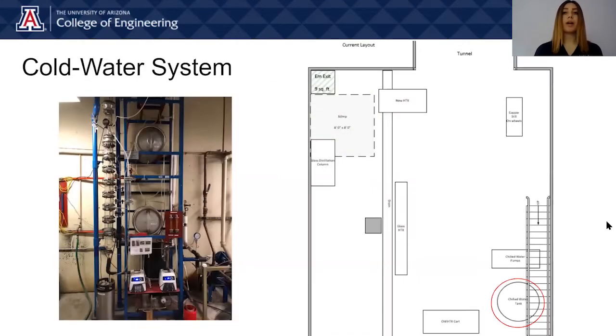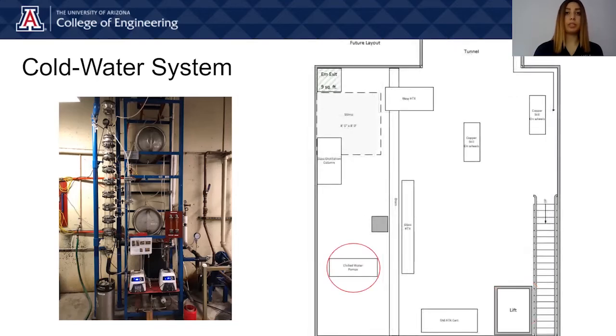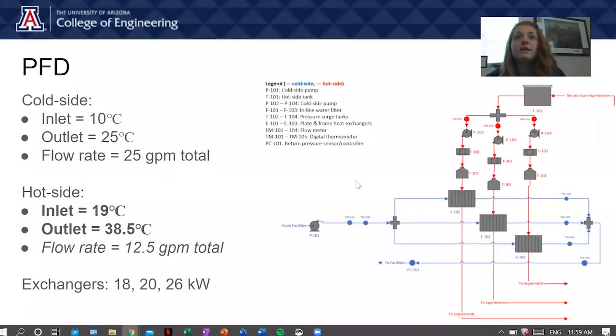The second part of our project is to design a tankless cold water system to provide cooling water to experiments in the undergraduate lab space that we call the pit, like the distillation column on the left. The current cold water system is located under the stairs, however due to the installation of a lift down to the lab space, it must be moved to the southwest corner of the pit area. Our criteria included sizing multiple heat exchangers in parallel, along with pumps, temperature and pressure monitoring systems, and pipes to meet the needs of the three major experiments in the lab space.